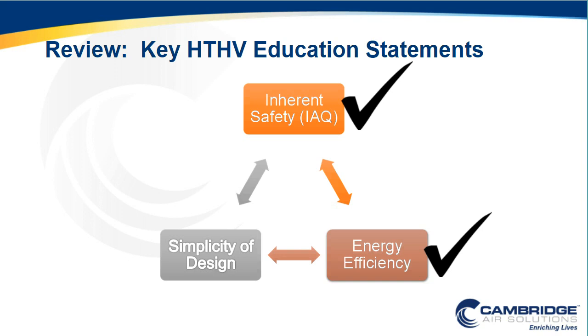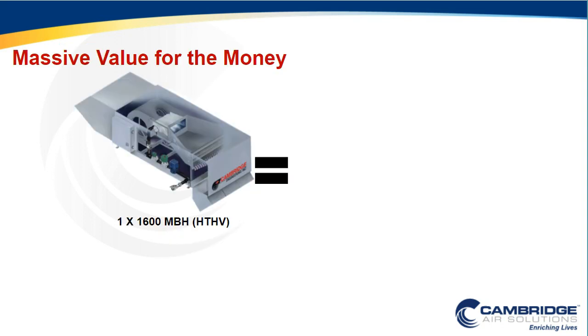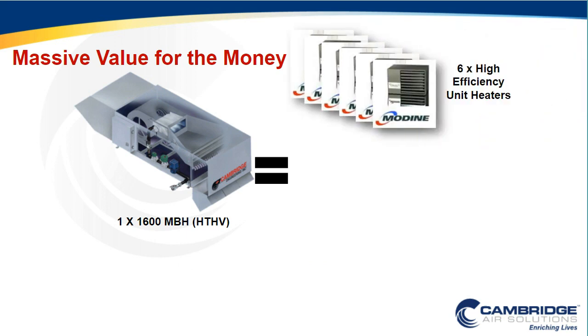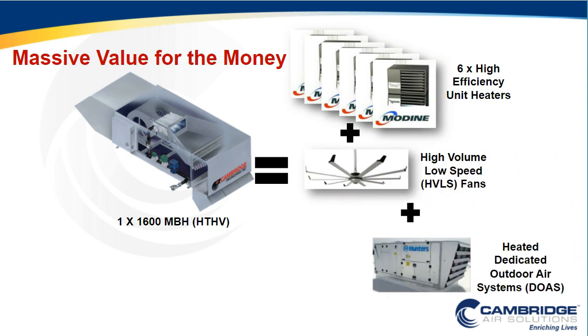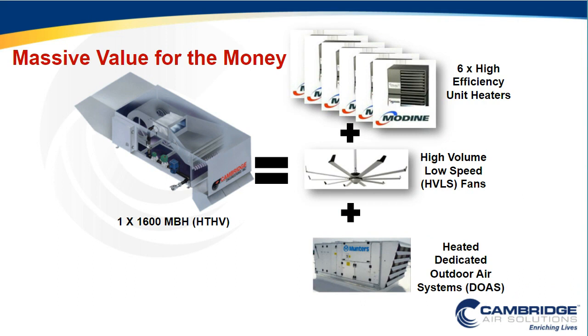So thirdly, the last, I would say, key pillar that we want to talk about in designing HTHV systems is, again, the simplicity of design. And I alluded to this a little bit earlier in our presentation, but ultimately a single HTHV system can replace multiple typical systems that we deploy in these spaces, which means greater value for the end user, and actually lower energy usage. So one 1600 MBH HTHV system also replaces the need for 6 high-efficiency unit heaters, some element of destratification device, and some element of a tempered ventilation system, such that one gas connection, one electrical connection, one blower can achieve my heating, my destratification, and my ventilation requirements.